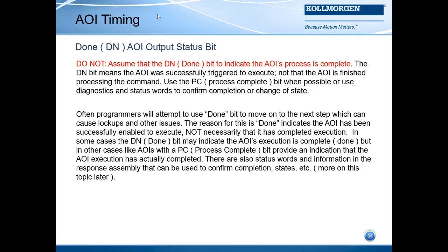The done bit on the add-on instruction output status. Do not always assume that the done bit is indicating the add-on instruction's process is complete. The done bit in many cases means the add-on instruction was successfully triggered to execute, but not necessarily that the add-on instruction is finished processing the command.